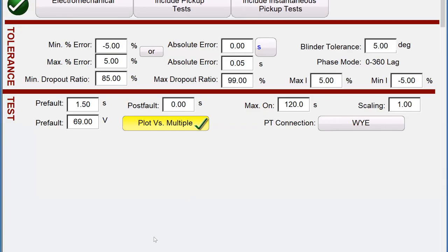Okay. All right. Since it's hard to run multiple things at one time, I think what's killing me is that the communication between my PC and the relay is not talking. It's not making good connectivity there. I am driving the test set, just so everybody knows. I'm injecting the current amounts like we talked about earlier on how we were doing the inverse curve.